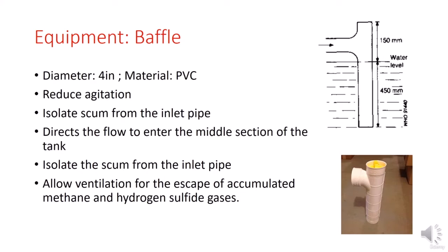Now let's talk about the piping system and the sedimentation tanks. As we have already seen, the diameter of all the pipes is 4 inches, and we are using baffles in all the inlets and outlets. So why baffles? A T-baffle helps reduce agitation, which is very important to consider in any sedimentation process. If the water is agitated, we won't have a proper sedimentation.